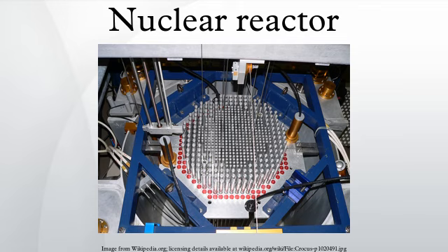Xenon-135 accumulation can be controlled by keeping power levels high enough to destroy it as fast as it is produced. Fission also produces iodine-135, which in turn decays to new xenon-135. When the reactor is shut down, iodine-135 continues to decay to xenon-135, making restarting the reactor more difficult for a day or two. This temporary state is the iodine pit.